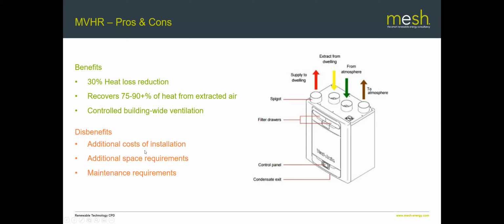So what are the downsides? Well, clearly there's a fair chunk of cost in the installation of such systems. There's ductwork to put in, there's designs to be done, there's space to be left for them. So there is some cost there, and of course, as with any system, there is a maintenance requirement. Any mechanical system is going to require some maintenance, but most of that maintenance is fairly straightforward. It's really changing filters and doing a bit of general spring cleaning.